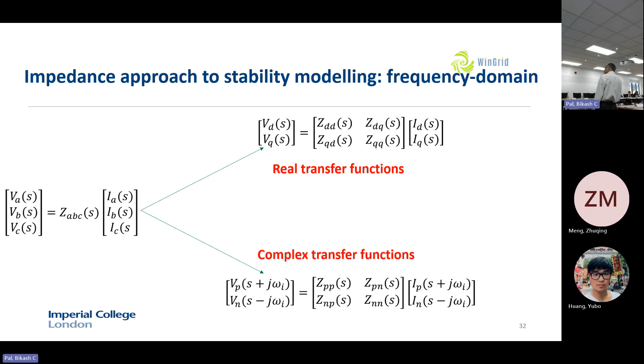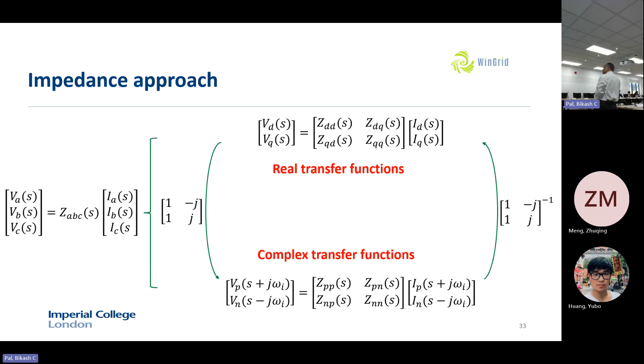Now we need to see the impedance, how the grid sees the whole wind farm as a variable impedance at different frequencies. So this one, typically this is the positive, negative, and then we do Nyquist stability analysis. The limitation is it only applies to a single converter to infinite bus scenario. So we always see that.